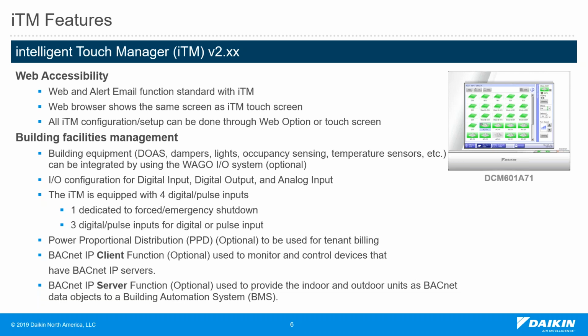The power proportional distribution function is optional. A license needs to be added to the ITM based on the application, most likely in a tenant building. This function could also be added to the ITM. Also the BACnet client function. From here, the ITM will act as a mini BMS. So the ITM can monitor other devices over the BACnet IP protocol. The other function is the BACnet IP server function. In that case, we are serving data points to the BMS. So the server works as the opposite of the client. The BACnet IP server means we are serving data to a BMS. Most likely we'll have a BMS at the job site, and both functions are using BACnet IP.